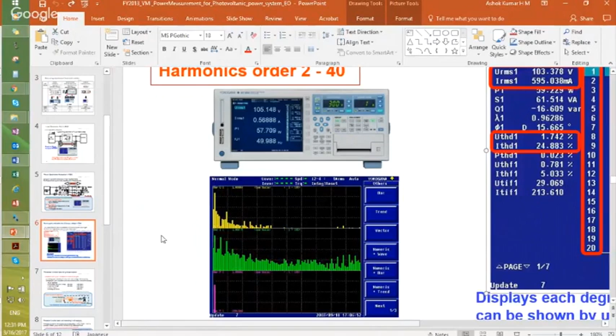This is the total harmonics display up to 500th order. As of today, the WT1800 is the only equipment which can give you detailed analysis up to 500th order. And as per the IEC standard, conformity to the IEC test of harmonics, IEC 61000-3-2 and 3-12. These two standards define the harmonics.